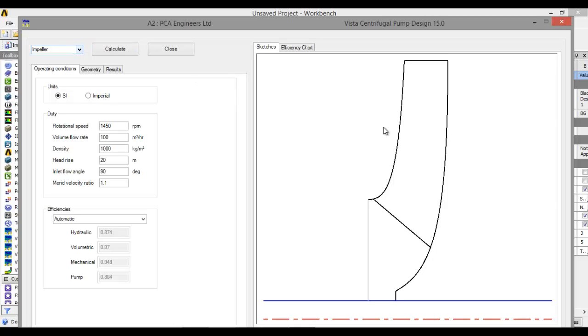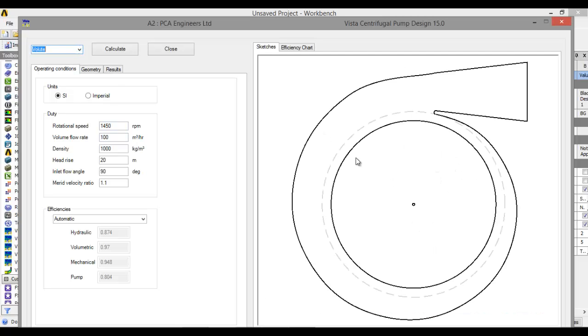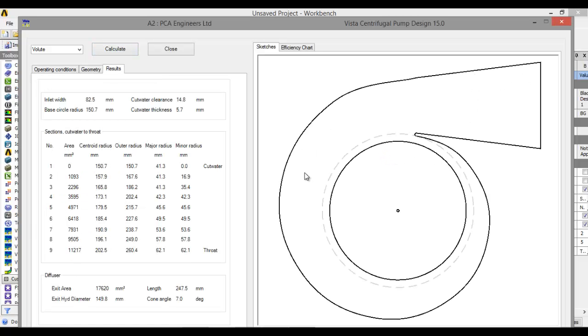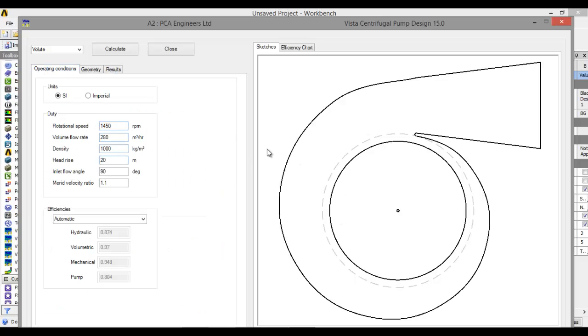Now let's see what kind of impact we see on the volute. Remember this condition: 1450 RPM volume flow rate. Click on it — here we see the volute. Now let's change the flow rate to 280 and click on Calculate. We see that there is an increase in width and other dimensions. So if we increase the volume flow rate, there is an increase in area and volume in the volute.